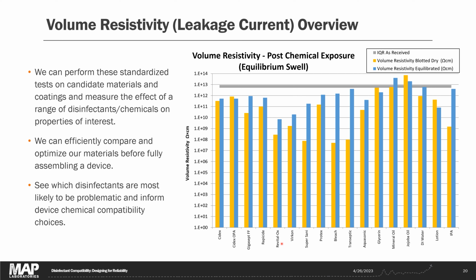And in this case, we found that Revital-Ox Resert, Super Sanicloth, bleach, transeptic were some of the worst materials as far as diffusion and changing the electrical properties of the material. It's not maybe realistic, but the worst case scenario is useful, both for seeing which disinfectants could be problematic and for comparing various materials. If we had another material that showed only 1 or 2 orders of magnitude drop in electrical leakage in that worst case scenario, maybe we should consider switching to that material.